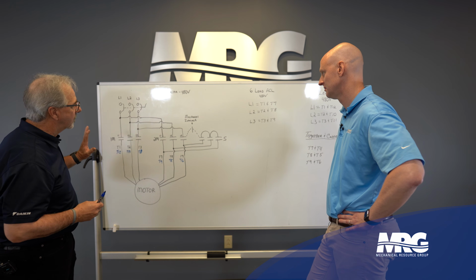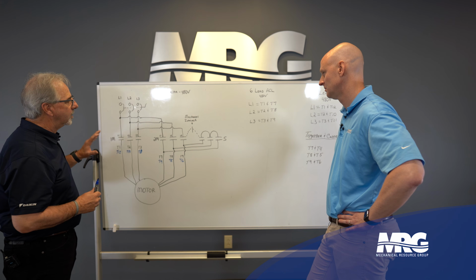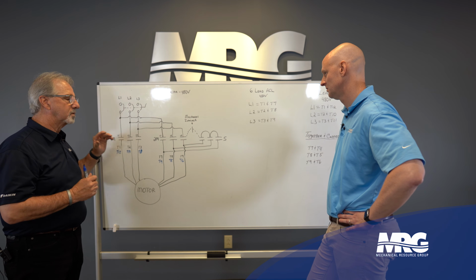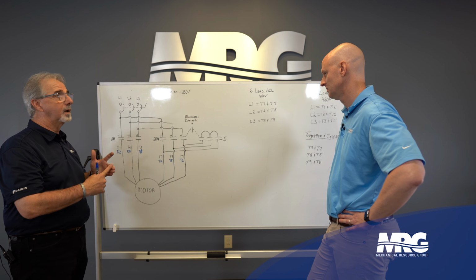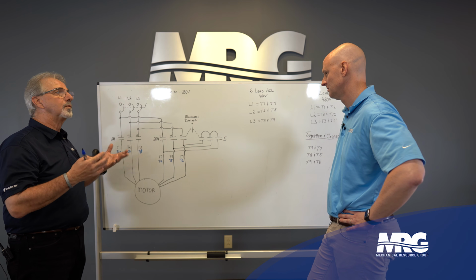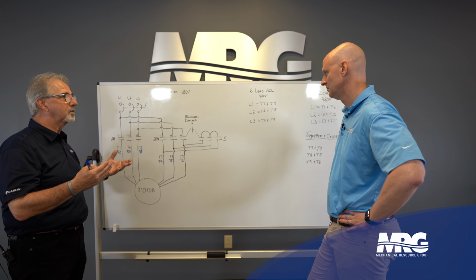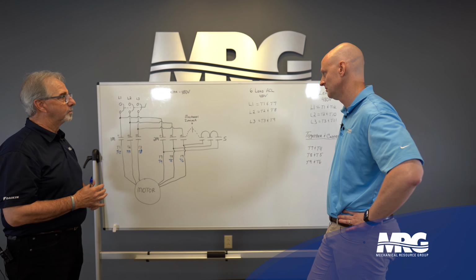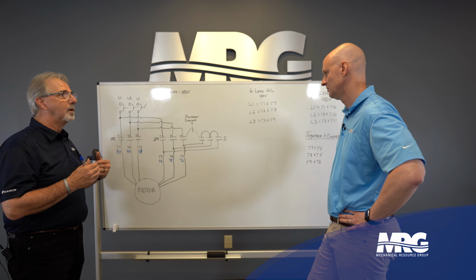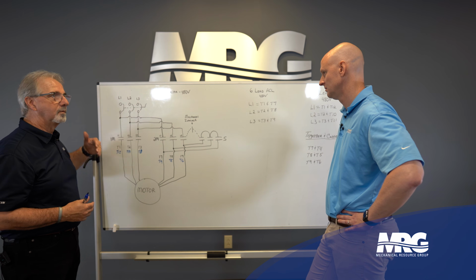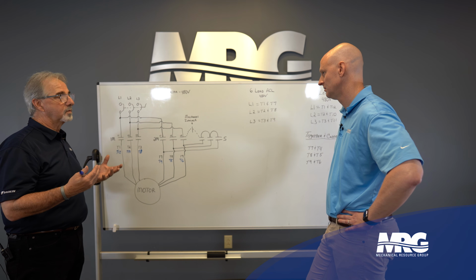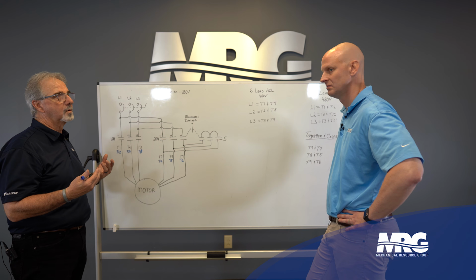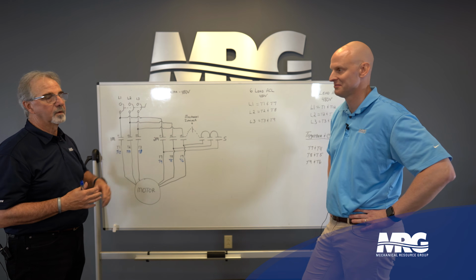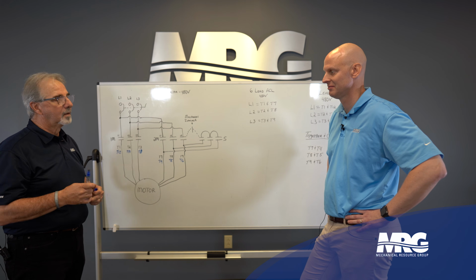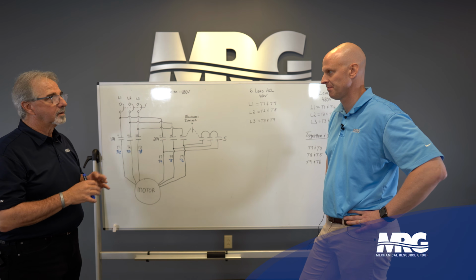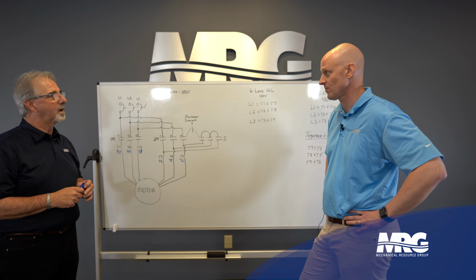And so the thing I'm trying to get across is, we need to make sure of the type of motor leads that you have. Do I have 6-lead? Do I have 12-lead? Do I have 3-lead? Do I have 9-lead? Those are the things that you need to know before you ever start connecting and hit a start button, because there is no coming back. Now, obviously we have circuit breakers and everything else that we hope will clear, but sometimes they don't, John. Sometimes that current is so quick, it'll exceed the rating of the contactor. Okay? So hopefully I kind of cleared up some of the connection methods that we use.